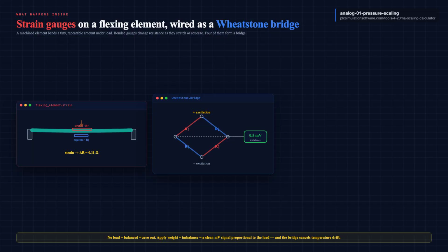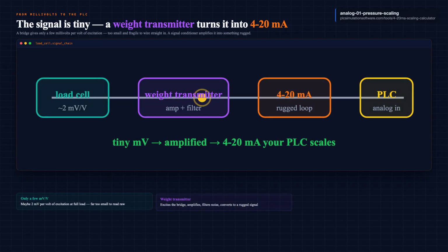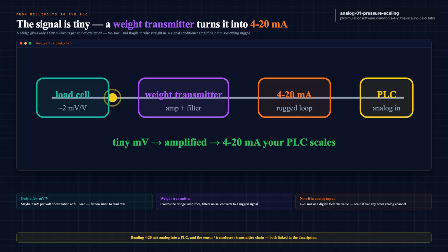Here is the catch. That bridge output is tiny. We're talking a few millivolts per volt of excitation. A typical cell might give you 2 millivolts for every volt you feed it at full load. That is far too small and far too fragile to wire straight into a PLC. So it goes through a signal conditioner, often called a weight transmitter or load cell amplifier. It excites the bridge, amplifies that whisper of a signal, filters out noise, and converts it into something rugged, usually a 4 to 20 milliamp loop or a digital value over a field bus. Now your PLC reads it like any other analog input.